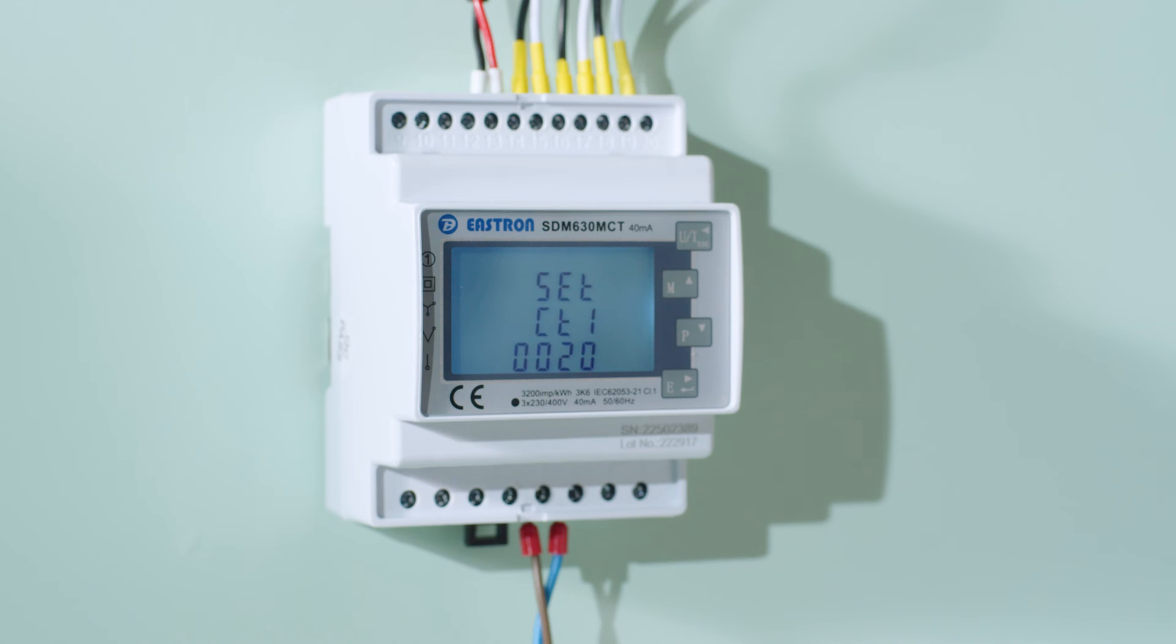Step five: Select Set CT1 and fill in the primary current corresponding to the clamps used. For the clamps we use, the primary value is 120 amps. Hold the E button until the first number starts flashing. Adjust the value using the up and down arrow buttons. Hold the E button until the display shows GOOD. The settings should be saved now. Press the UI button to exit the menu.